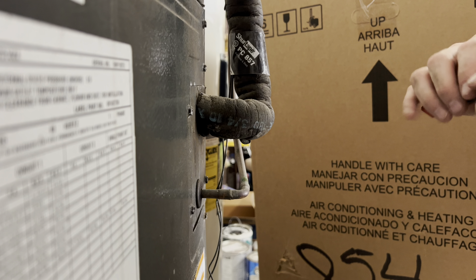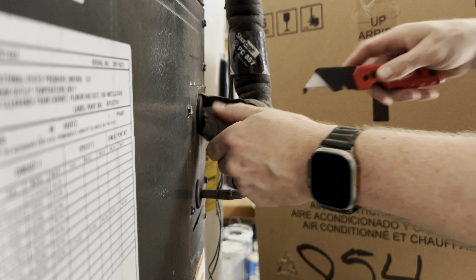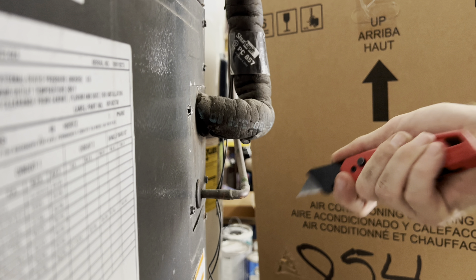So we just go get up in here, cut this copper loose, braze in the new coil, purge nitrogen — of course, because you're out there — and then evacuate, charge it, and get on to the next one. I've said this numerous times on this channel — what I like to do is...